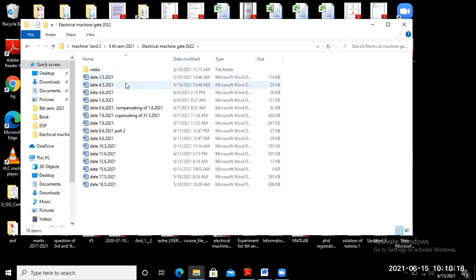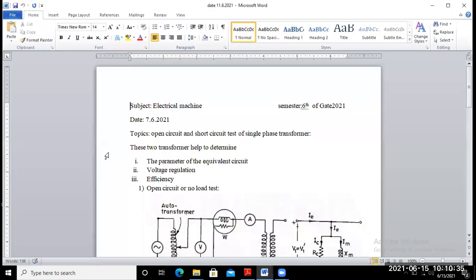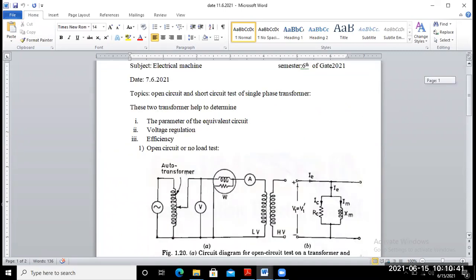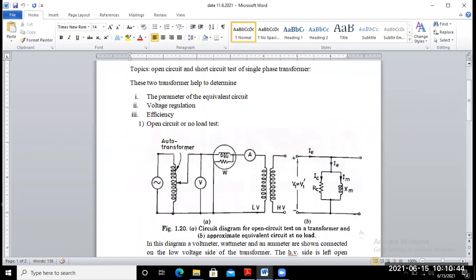All the measuring instruments we require, that means voltmeter, ammeter and wattmeter, are connected to the LV side winding. So this is the equivalent circuit connection for the open circuit test. The HV side winding is kept open and on the LV side we connect the instruments: one voltmeter, one wattmeter and one ammeter.